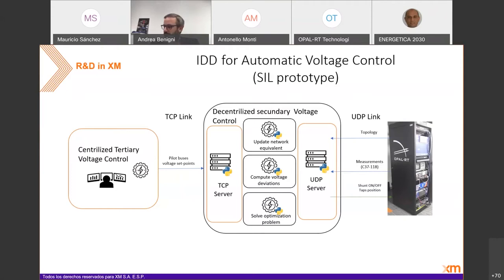Once this is done, we have another network simulation on the separate computer that runs this short network, updates the equivalent, and computes the voltage deviation from the pilot buses versus the set points from the tertiary controller. Finally, it solves an optimization problem that commands movements or positions of the tap changers and shunt devices, and in the future, we think we can also incorporate set points for generator exciters.